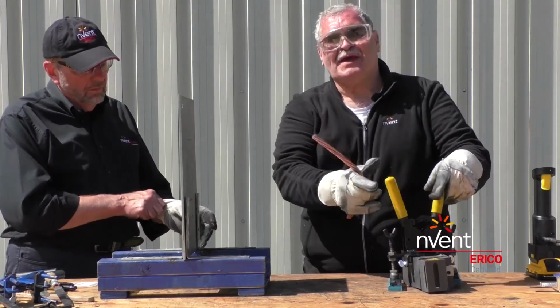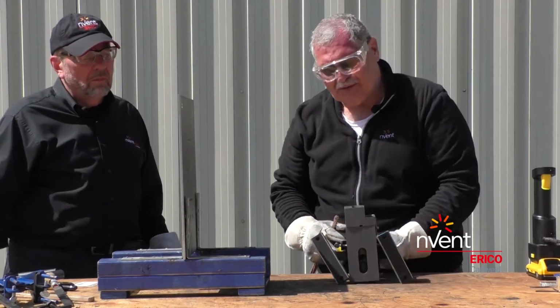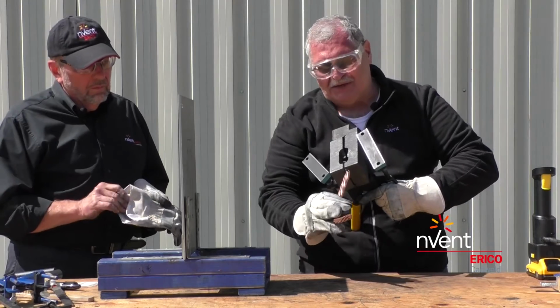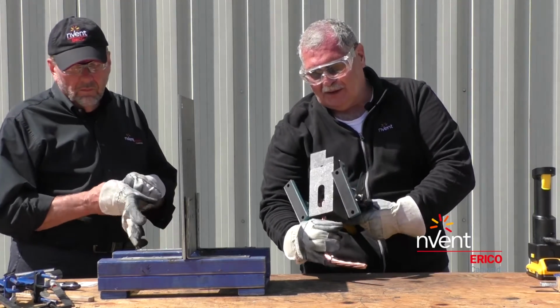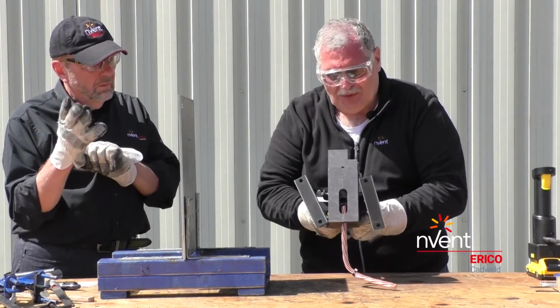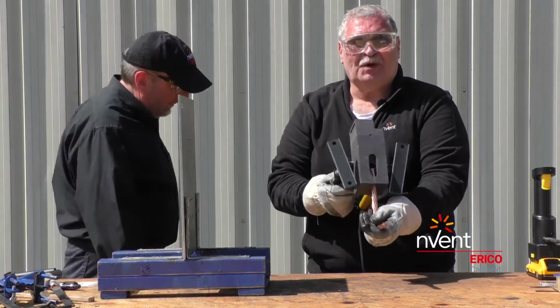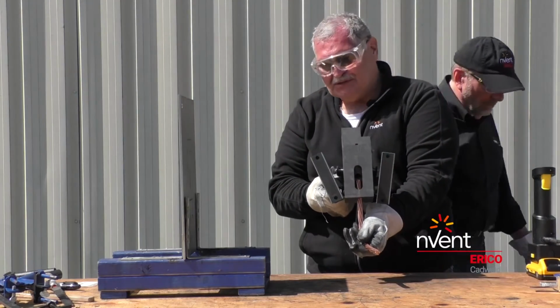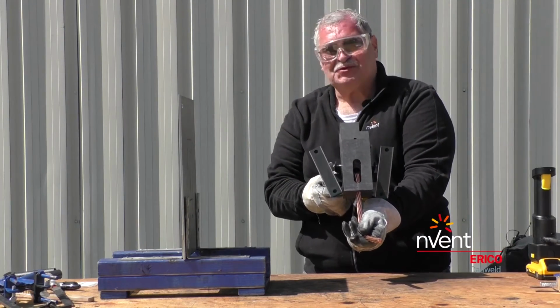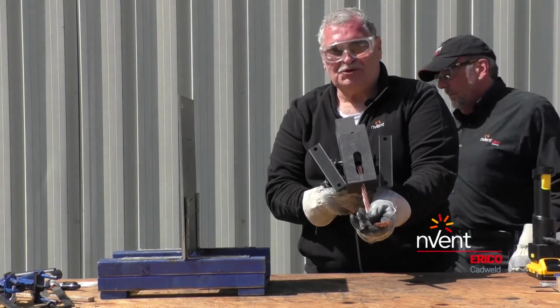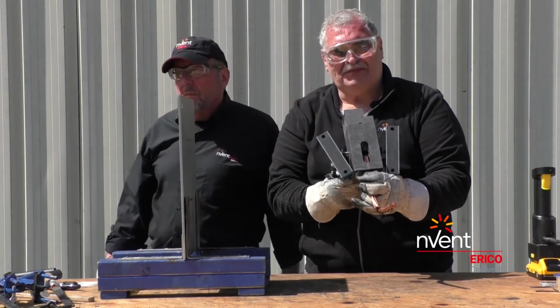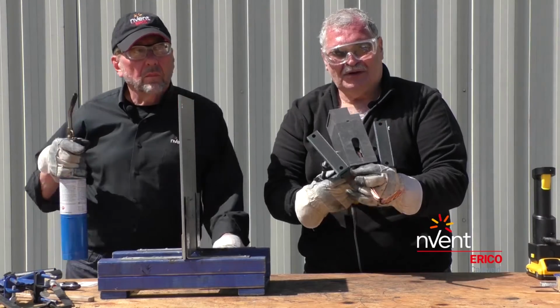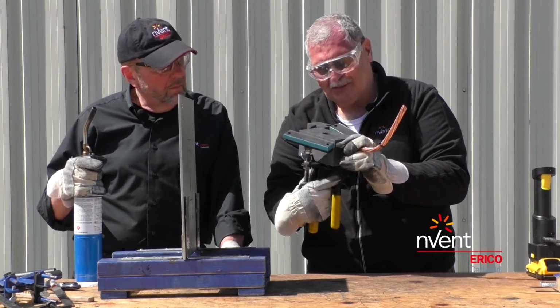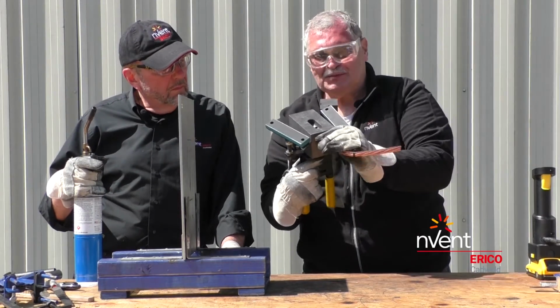When I'm placing my cable in a VB mold, everybody has a tendency to put the cable in, clamp the mold, and push it all the way up to the top. What happens is you usually leave some strands unwelded. So what you want to do is bring it down about 1/8 of an inch. You can take a peek at it and say, yeah, that's about 1/8 of an inch. And I'm going to spin this way.